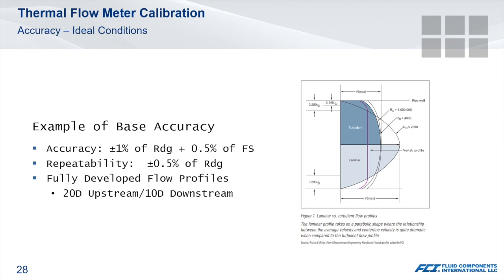Regardless of the technology, published accuracy is based on ideal conditions. When calibrated at the factory, ideal straight runs ensure that velocity profiles are fully developed. Often these ideal conditions are hard to come by in the field, especially in larger line sizes. Elbows, valves, and other obstructions within a meter run will result in distorted velocity profiles. Be sure to work with knowledgeable manufacturers that can help you better understand meter accuracy under actual conditions.